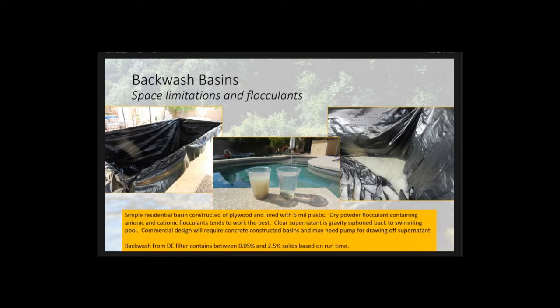From a commercial perspective, we've got to worry about if we've loaded up the biologicals, bacteria, into that filter, we don't want to recover highly polluted water back in. So we may, on the industrial side, add some hyperchlorination to just that water, or other advanced disinfection technologies to treat that water specifically. But certainly thinking about how we take industrial water recycling and reuse that. And I reuse 95% of the water from my backwash. So significant reduction in water usage.